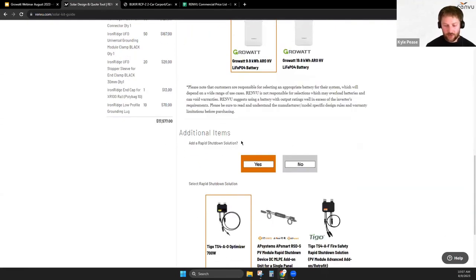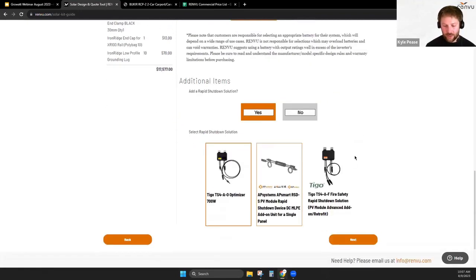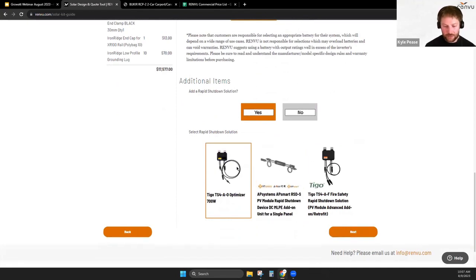If it's going on an inhabited dwelling roof, then you'll need to have rapid shutdown, and while you're at it, you might as well add optimizers if you can do it. It's all in one unit that needs to go on each module to be able to shut it down. So depending on your project, you may or may not need these. If you're putting these on the roof of your house in the US, you will need, as a minimum, just a standard rapid shutdown. And then the optimizers provide mitigation for shading concerns on the array. If your array has partial shading, these can help alleviate that, similar to microinverters.